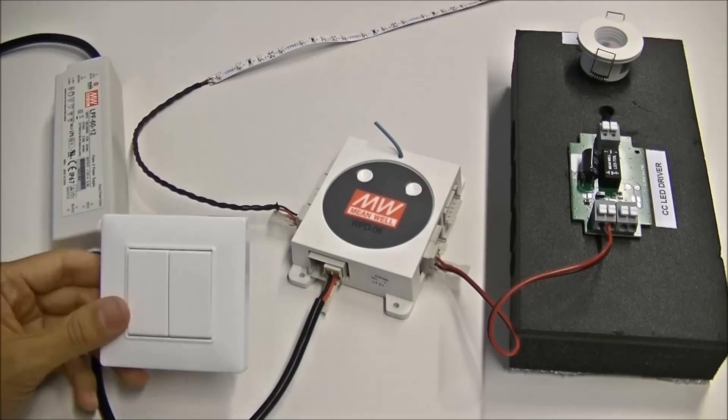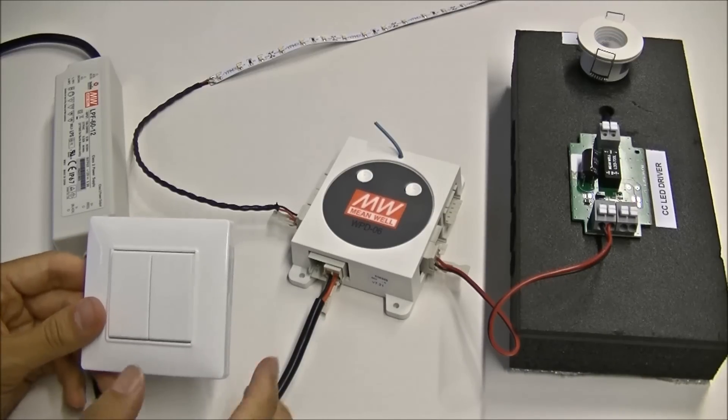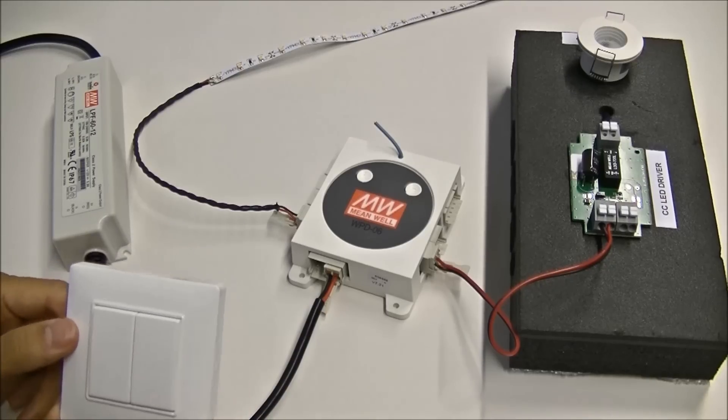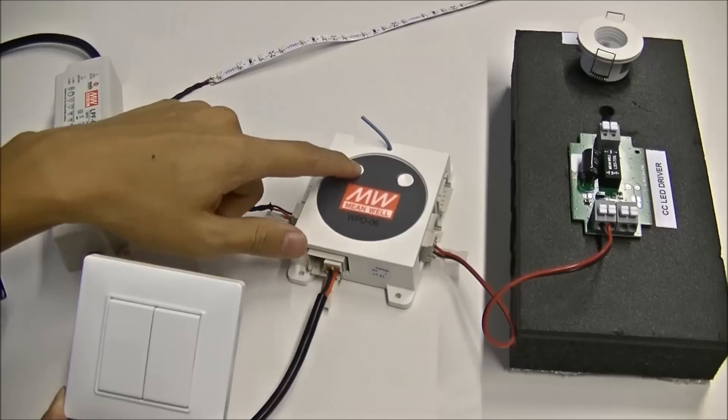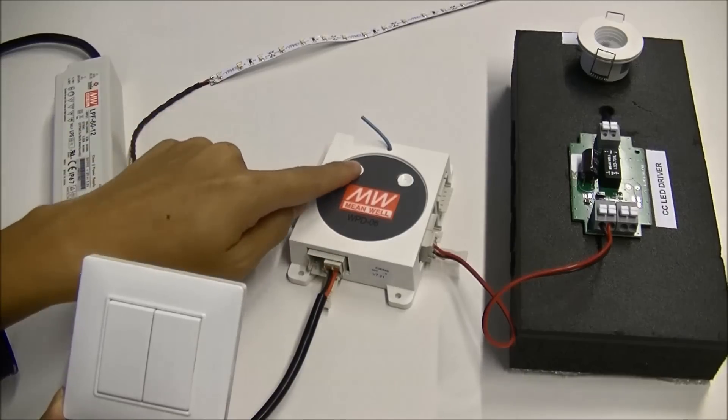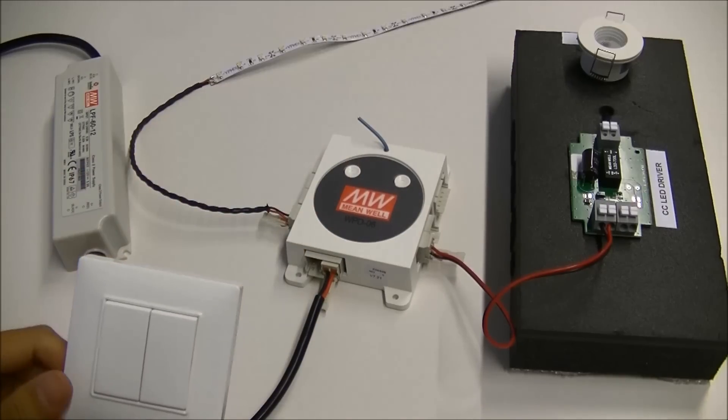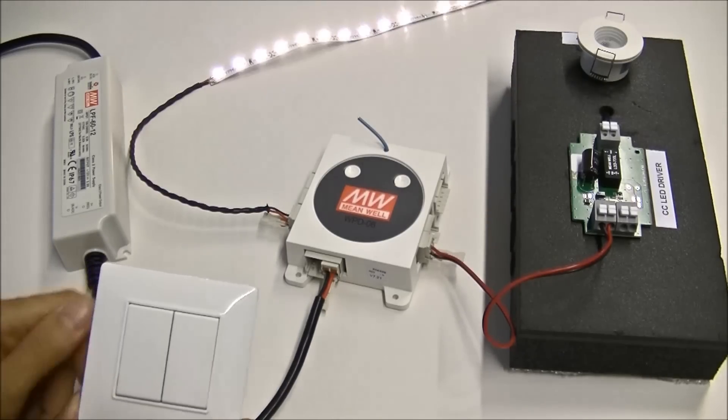Before the pairing, make sure LED driver or power supply is powered. Now press L button of dimmer. You will see channel 1 is now blinking. You can press the switch to set it as a turn on command.